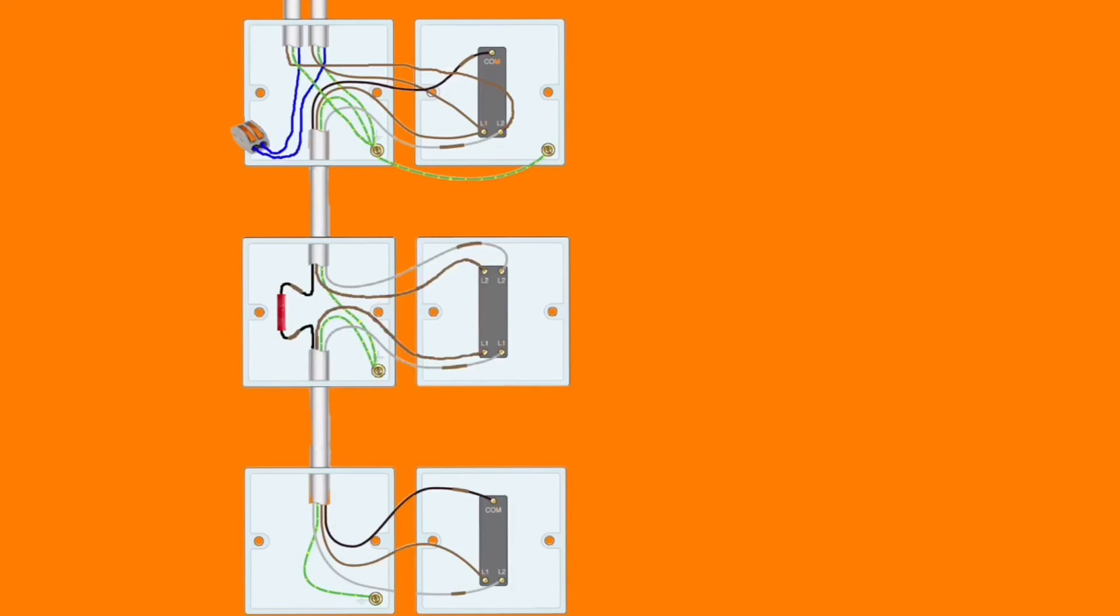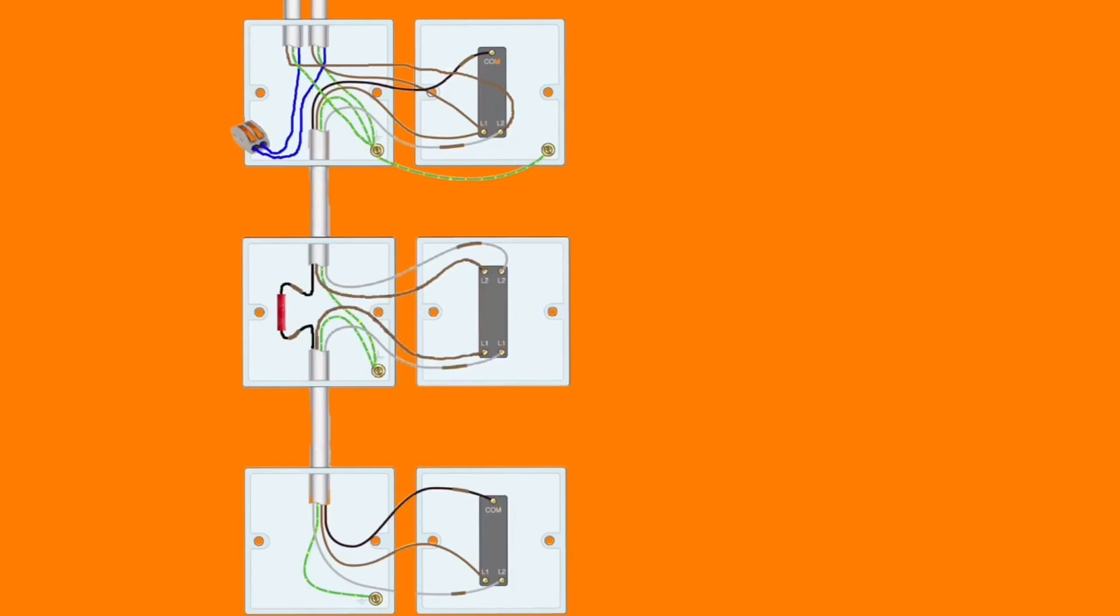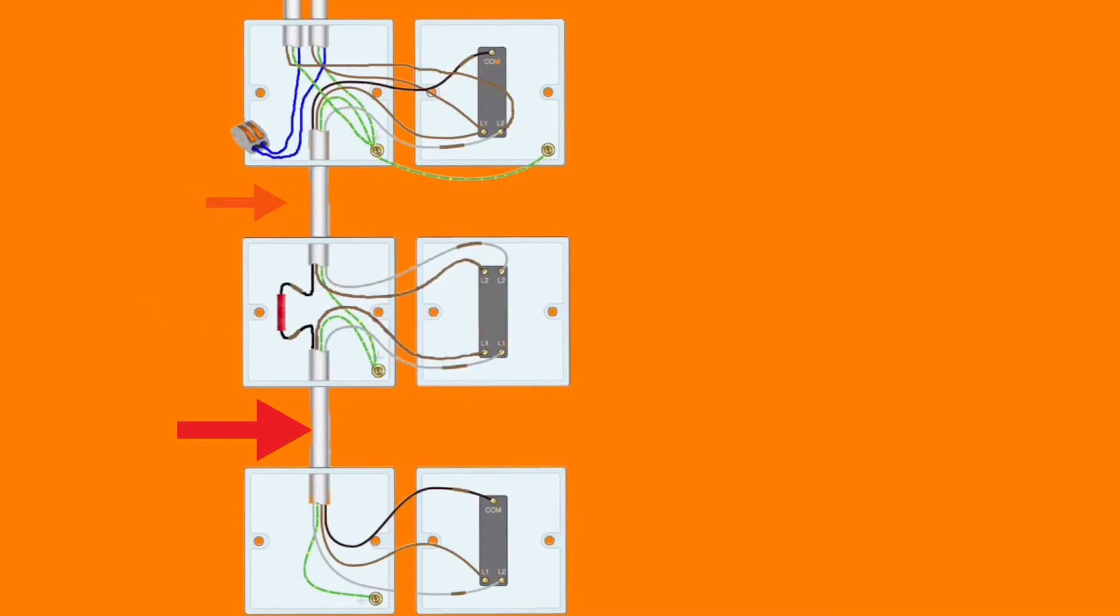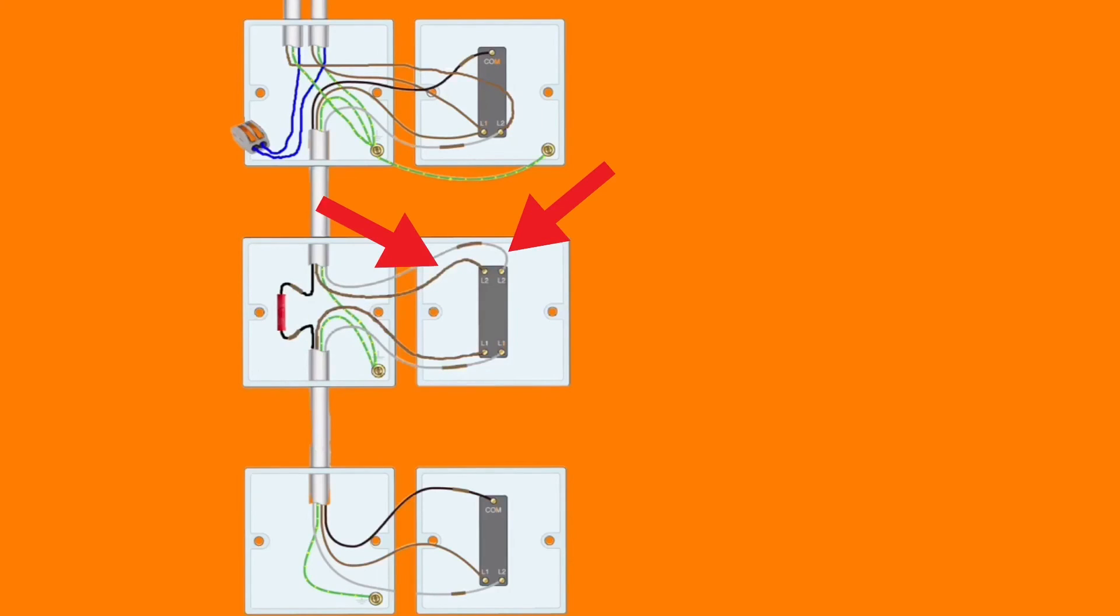The black conductor within the intermediate switch on both sides of the through crimp is identified with brown sleeving and is joined together. The three core either from the top switch coming down or the bottom switch coming up has its brown and grey conductor either connected in the bottom of the intermediate switch or in the top of the intermediate switch.